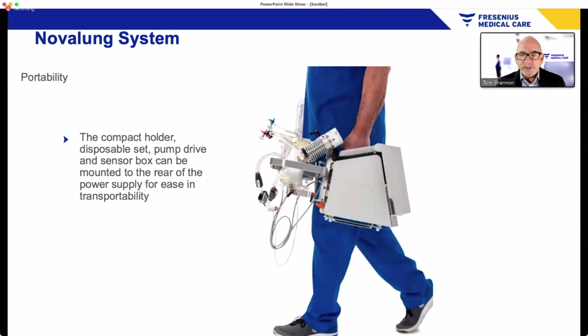The disposable, if you haven't seen it before, has integrated pressure sensors, and this is a unique system that we have that doesn't require zeroing these transducers ever. We have an FDA indication for ECMO and ECPR greater than 6 hours, and the sensors are unique in that they check ambient pressure outside the disposable as well as on the inner surface of the disposable, and it constantly does not require zeroing because of that.